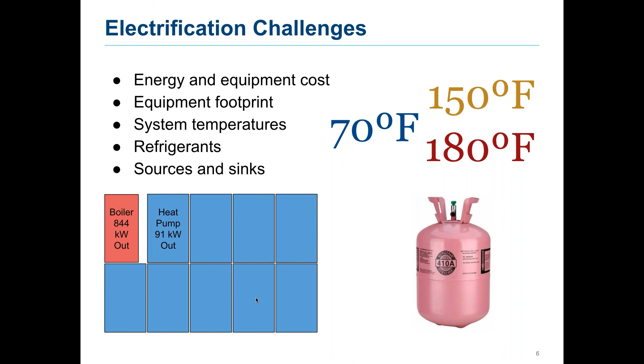The final thing we have to consider is sources and sinks. Heat pumps need a source of heat to produce heating—that's either air, which comes with some efficiency penalties, or, if we want to take advantage of synergies in our systems, we might want to reject heat into an existing cooling water system, but then we need to balance those loads. So there's some additional complexity in trying to capture these synergies.